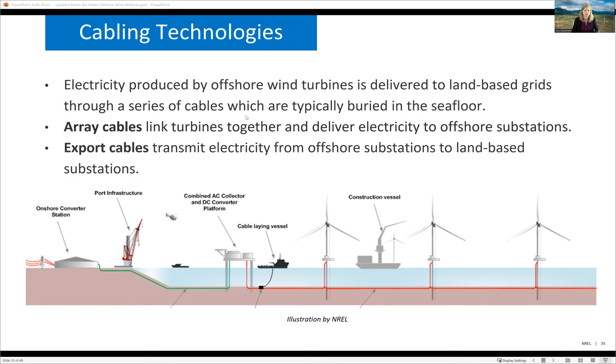You can see that we use both AC and DC types of cables. So when we talk about array cables, they're typically just AC type cables, and you can see here kind of the diameter range and the voltage rating. But when we talk about export cables, we see not just AC, but also DC types. And the reason we'd like to go to DC type cables for export is because those cables are going to be running over very large distances. And for AC, you start to lose power as you travel over long distances. And so DC can be more advantageous. And with these floating wind systems, especially, we may be putting them very, very far offshore, and that export cable may need to be very long to get that power back to shore.